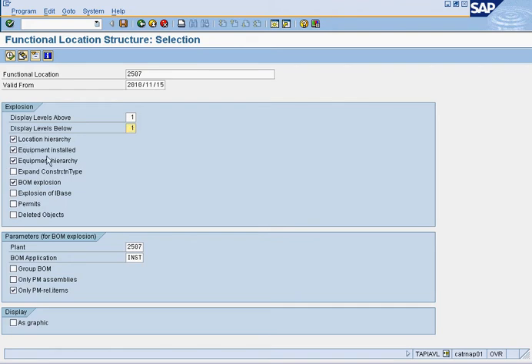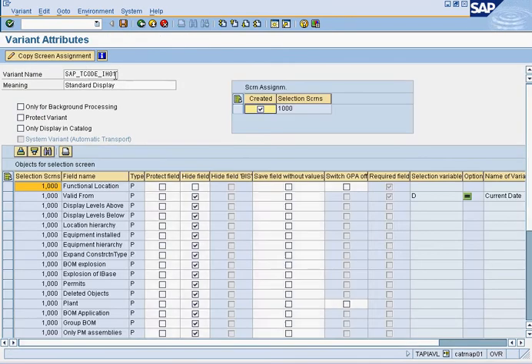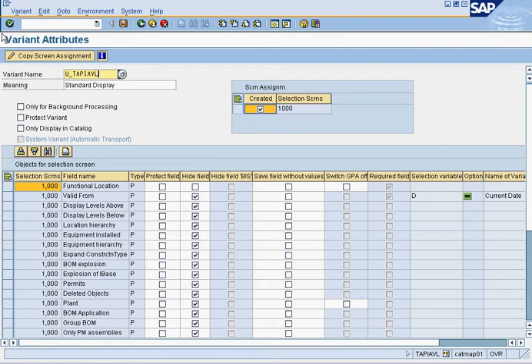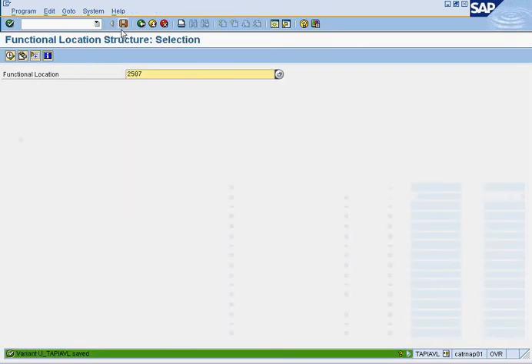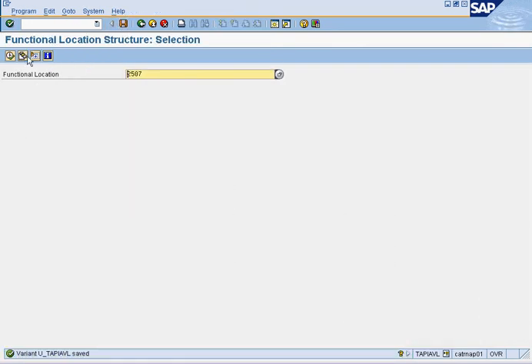The settings you want to have are: the plant, levels above and levels below set to 1-1, location hierarchy, equipment installed, equipment hierarchy, and BOM explosion with only PM related items. This is the way it should be set up in order for users to see the items they need. Once done, press save and put it under U underscore the user's name, then press save again.